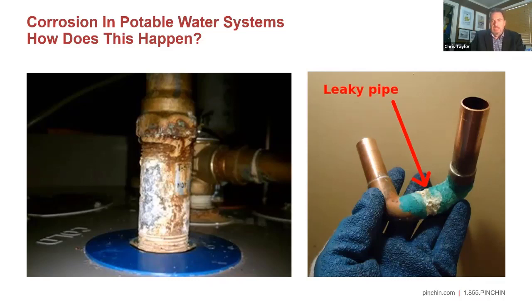We've had a couple of clients that have tried using shock chlorination on buildings that were completely not being used. And what they've found is that it becomes very difficult to actually funnel the shock chlorine system through all the piping, or that if they're flushing, they want to go through and turn all the taps on at once, but the water pressure doesn't get the type of water pressure that would help in reducing that biofilm.